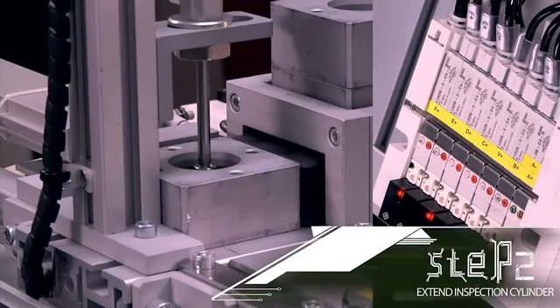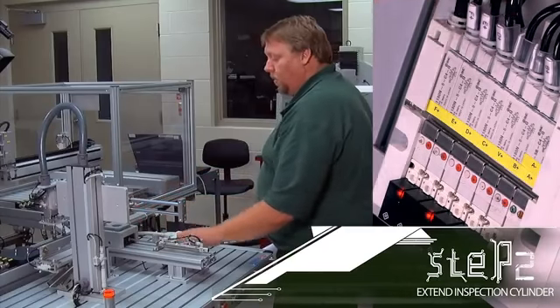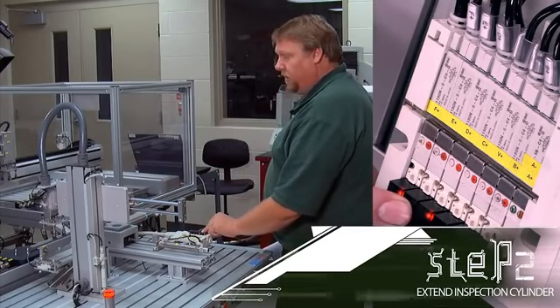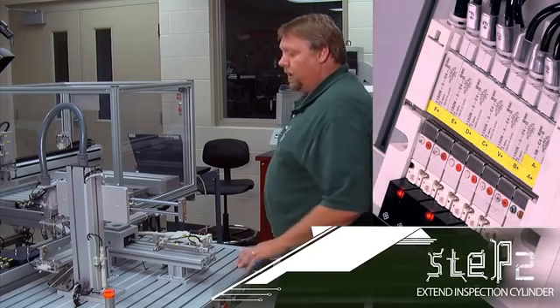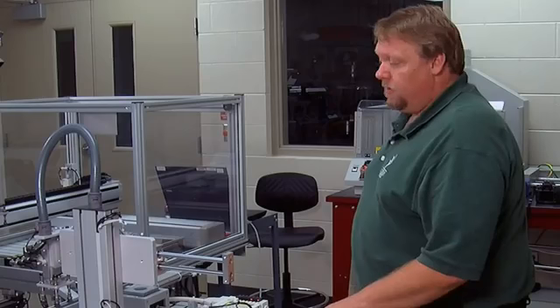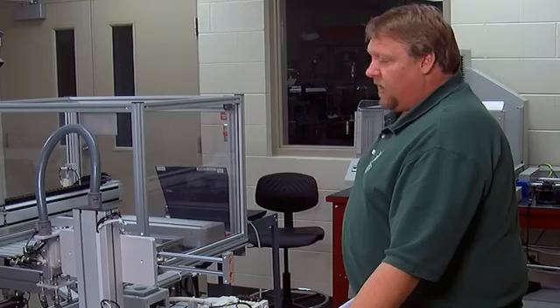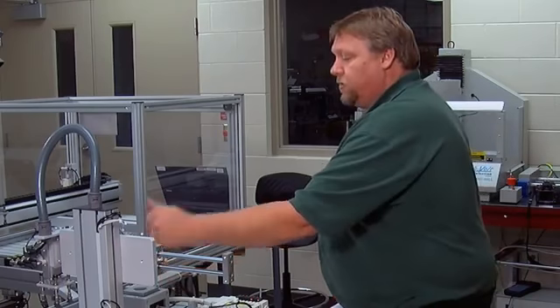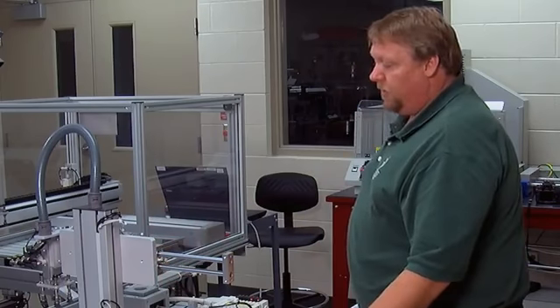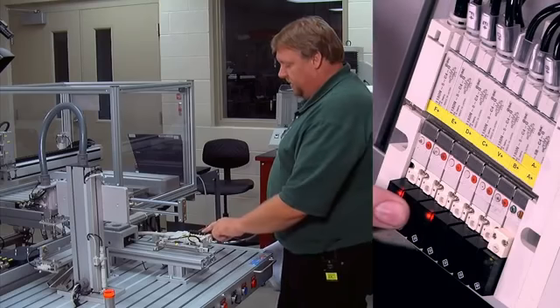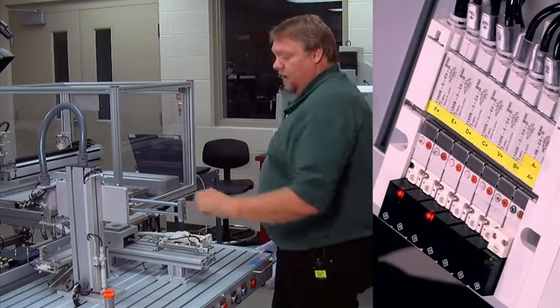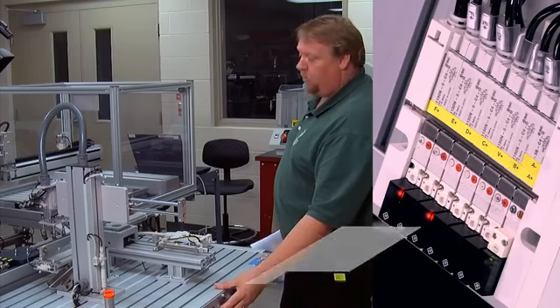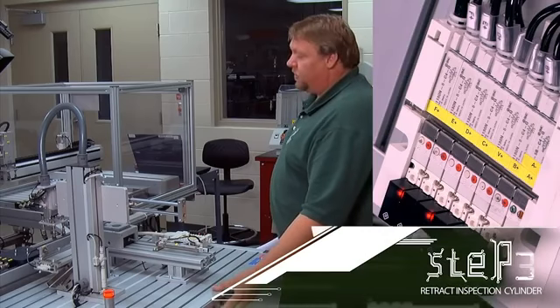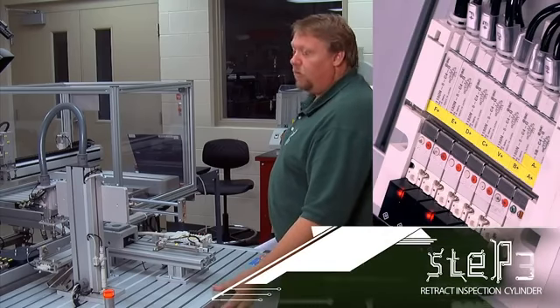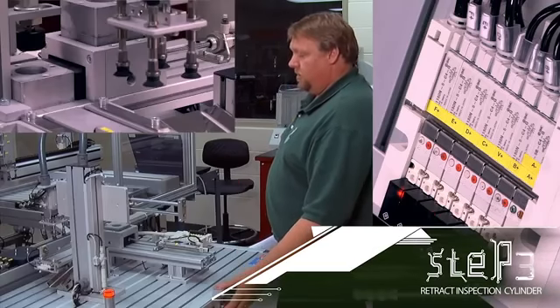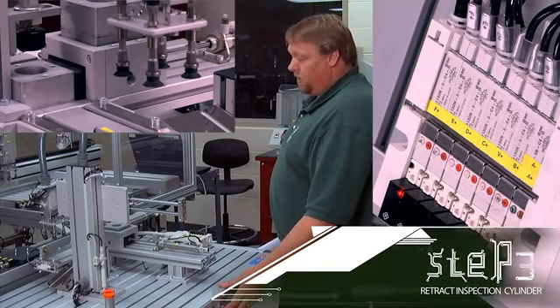Okay, the cylinder has extended, the input light is on, the output also to energize the valve is on, and now we are ready for step 3. Step 3 will be to retract the inspection cylinder, and at that point this light is going to go off and this light is going to go off, because you remember, if we remove the electrical signal, the cylinder will retract. Okay, and that is step 3.